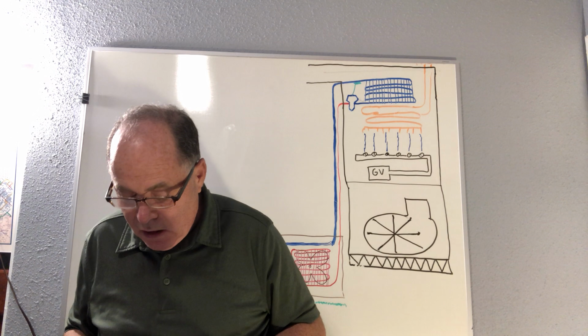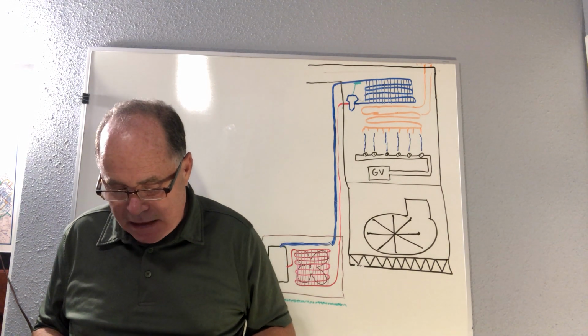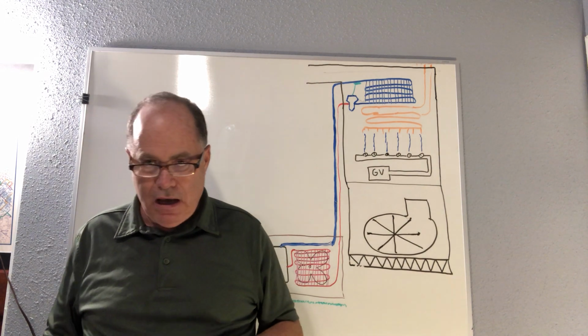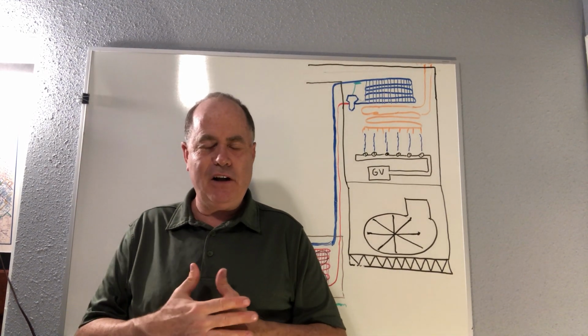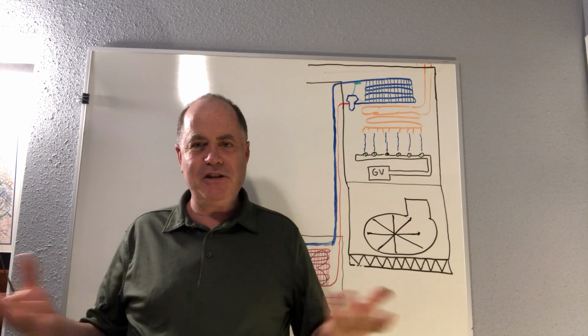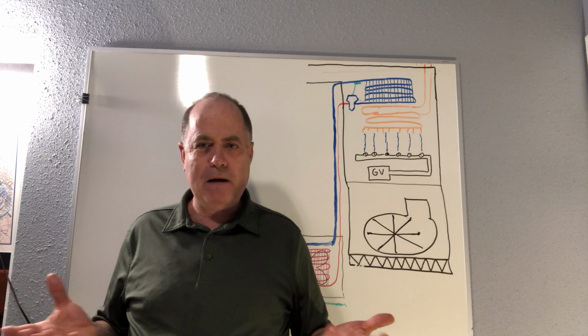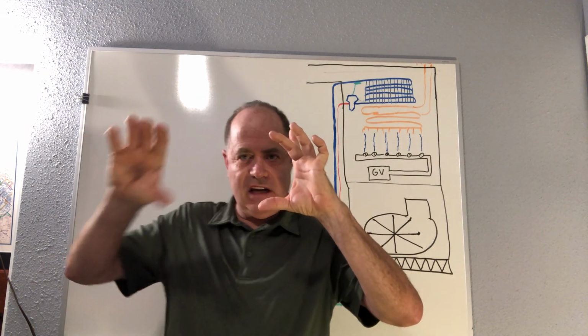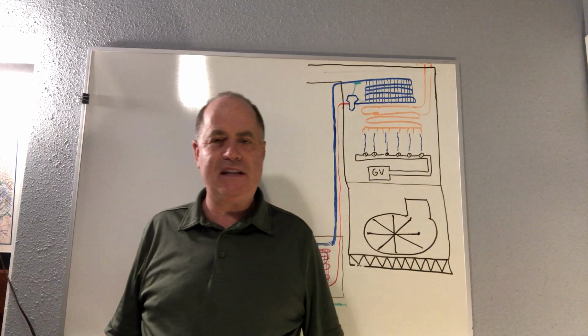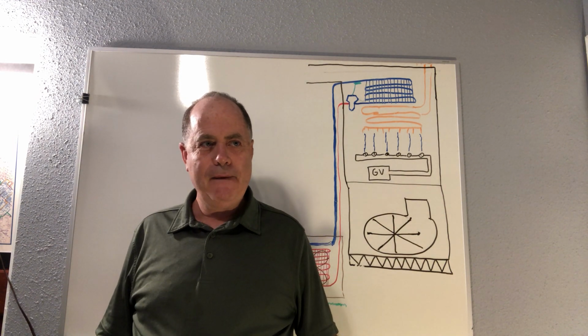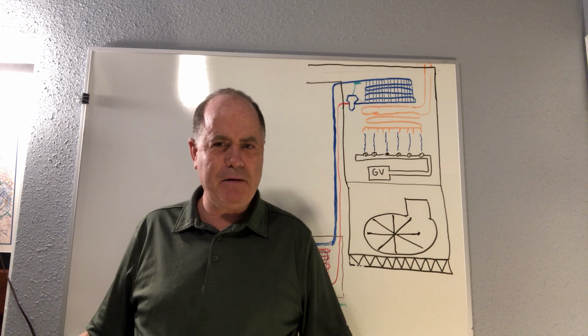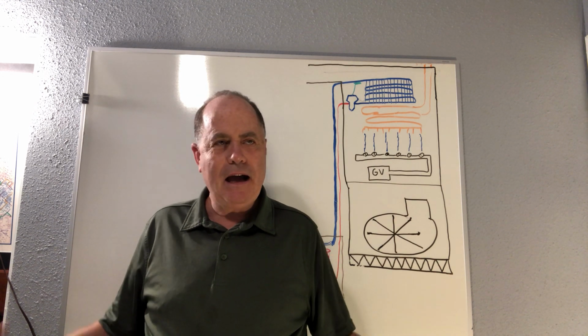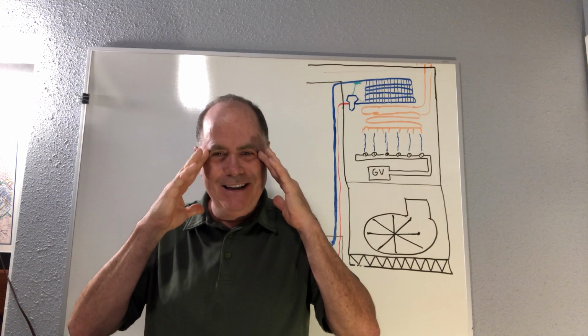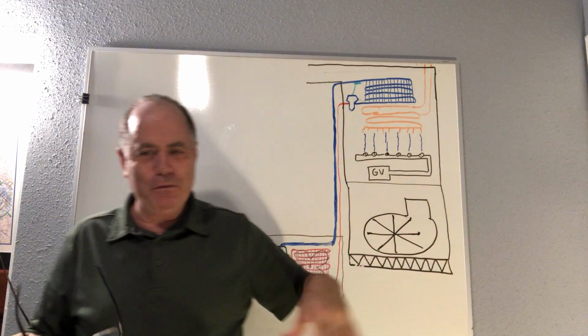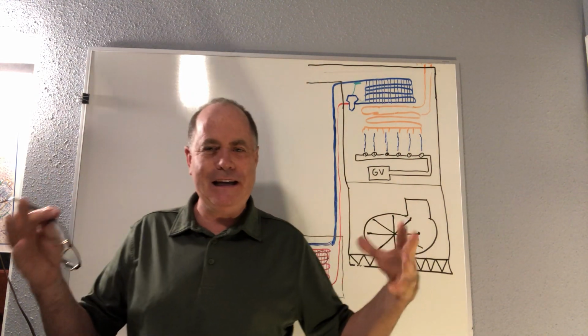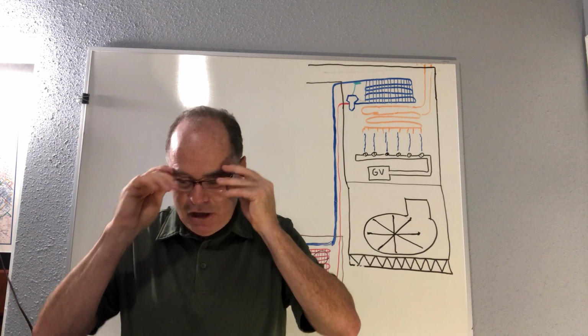All right. And then all dryers shall be exhausted to the outside atmosphere. And actually, I had a student one time who told me he thought of a great idea to save energy. In the wintertime, he just undid his exhaust pipe, the 4-inch corrugated pipe. He just took that off and let the warm air blow into his house. And he thought it was a great energy savings thing. And I said, well, isn't that portion of your house by the dryer really dirty? And he goes, I don't care. Yeah. I go, that's kind of a fire hazard too. So it's not good to have that products of combustion and water vapor and all that lint and everything blowing into your house. So that was an odd moment for me.